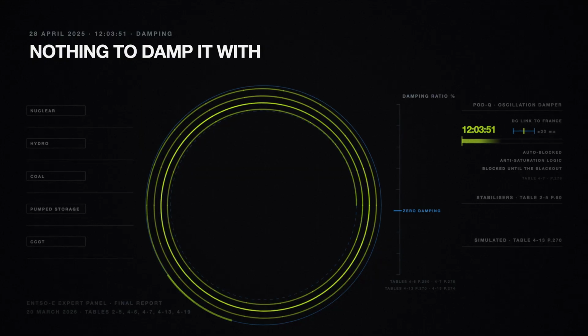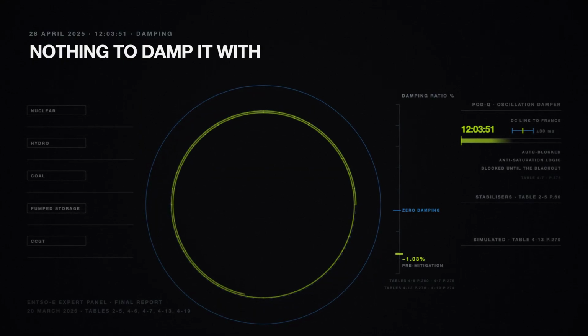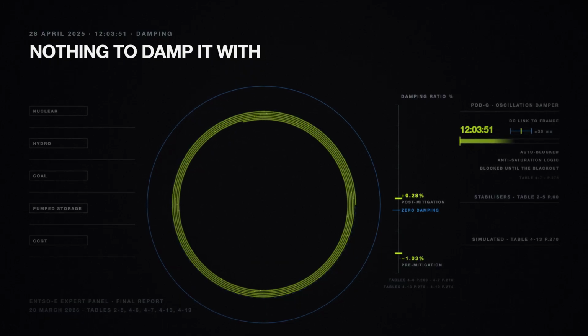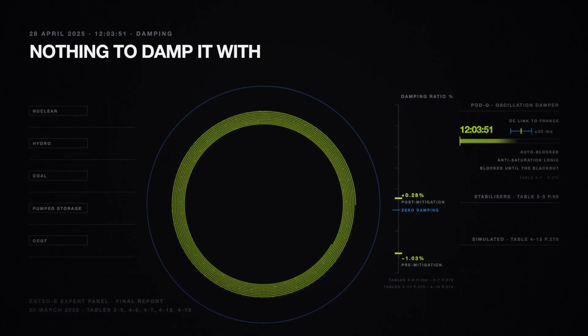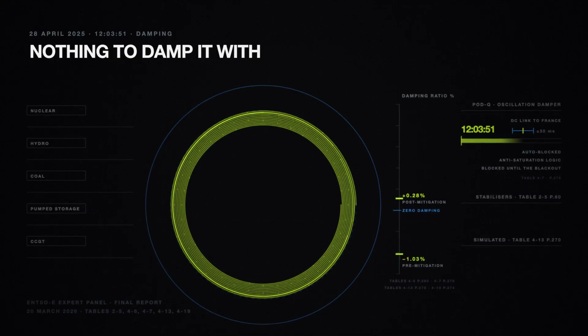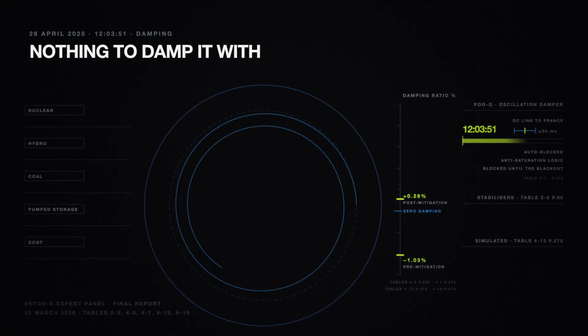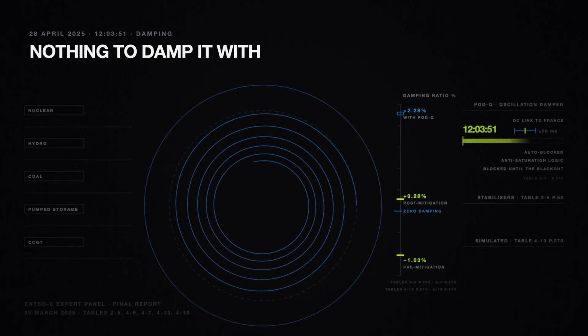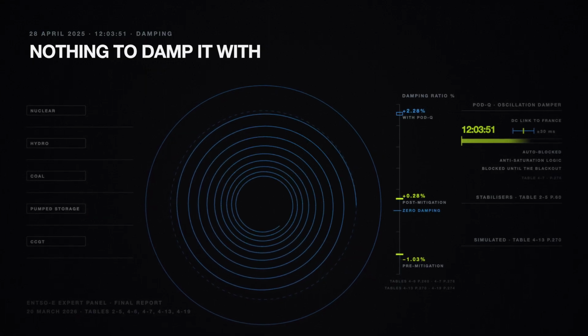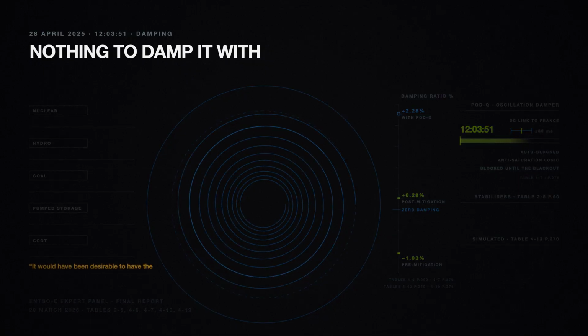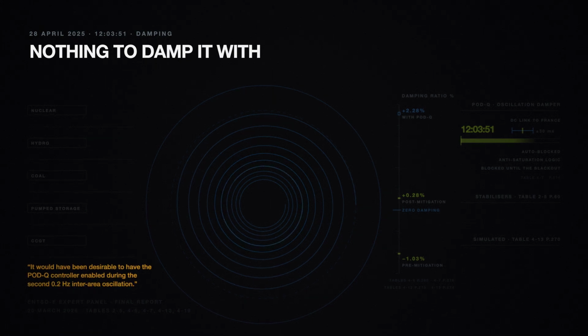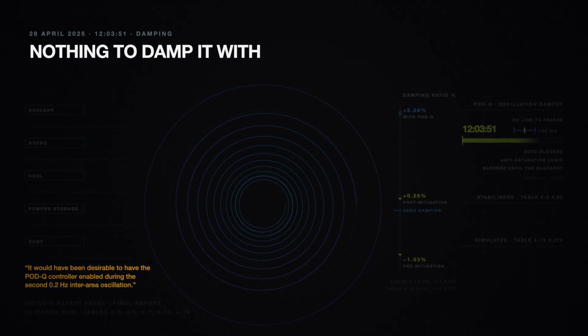The numbers it was blocked for. The inter-area mode measured before mitigation, minus 1.03%. After mitigation, plus 0.28. Had PODQ been available, the panel calculates the second episode would have been damped at 1.55% instead of 0.28. Its comment: it would have been desirable to have the PODQ controller enabled during the second inter-area oscillation.